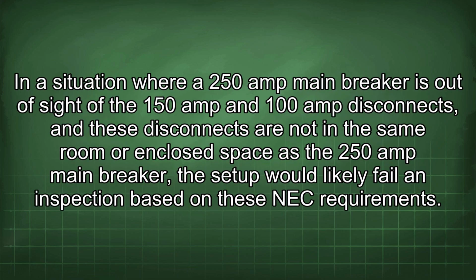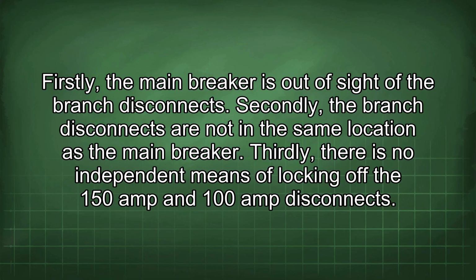In a situation where a 250 amp main breaker is out of sight of the 150 amp and 100 amp disconnects, and these disconnects are not in the same room or enclosed space as the 250 amp main breaker, the setup would likely fail inspection based on these NEC requirements. Firstly, the main breaker is out of sight of the branch disconnects. Secondly, the branch disconnects are not in the same location as the main breaker. Thirdly, there is no independent means of locking off the 150 amp and 100 amp disconnects.